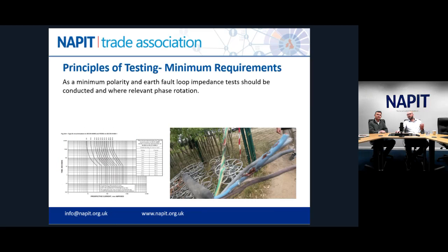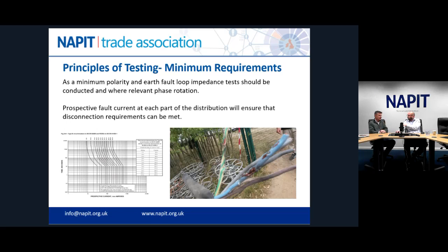Okay. So as a minimum, we want to check polarity and earth loop impedance tests, and they should be done at the relevant points as we've just discussed, and where relevant, phase rotation. For the most part, we tend to split things down into single phase loads, but quite often we will have three-phase appliances like a stage lift or a three-phase air conditioning unit. Obviously, if you've got a phase issue, then you might blow up the equipment. So it's important to make sure phase rotation is checked where it's appropriate.